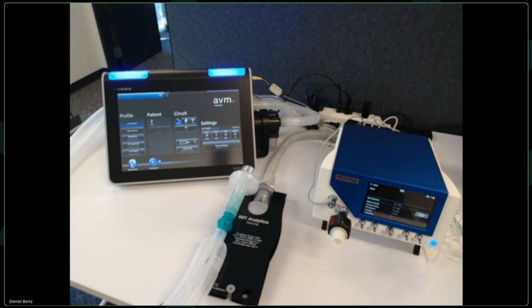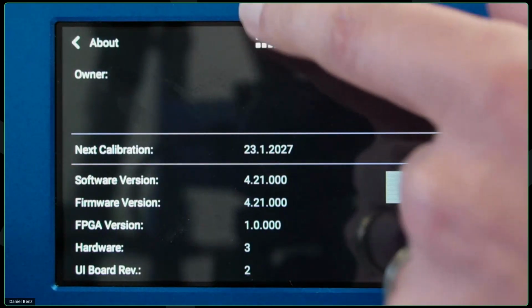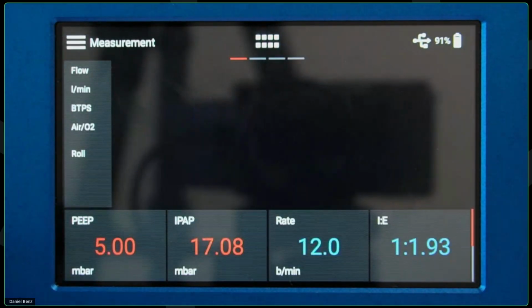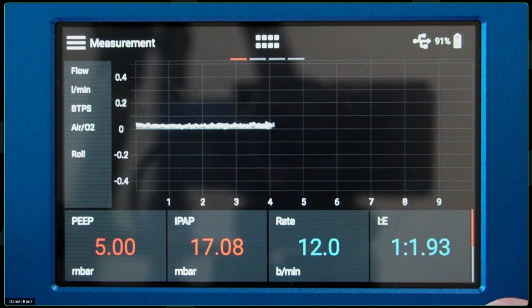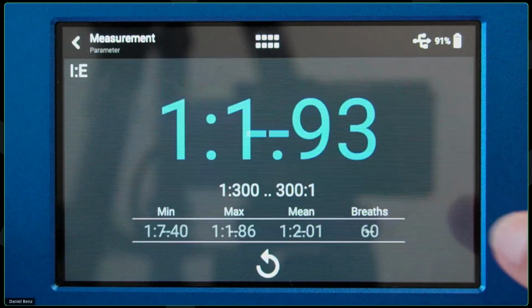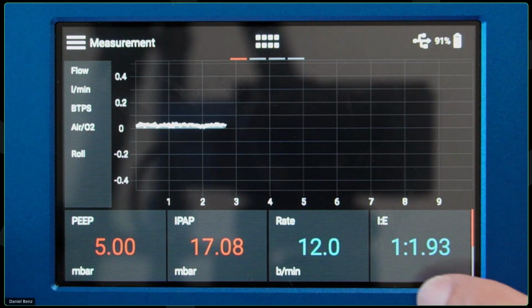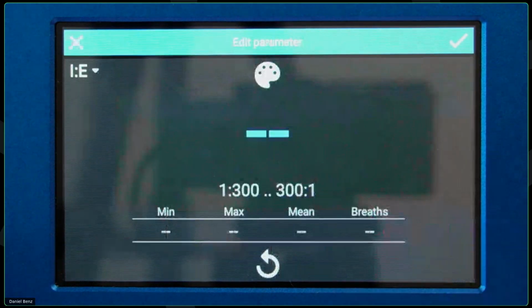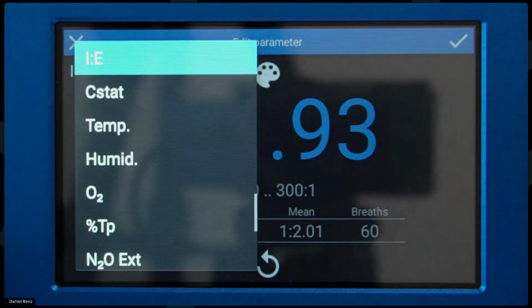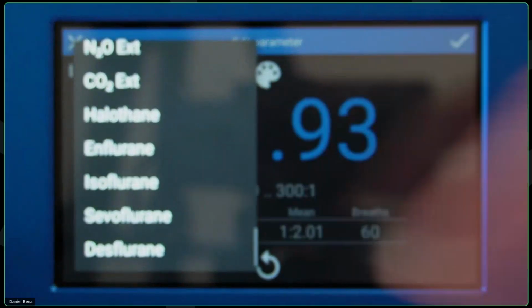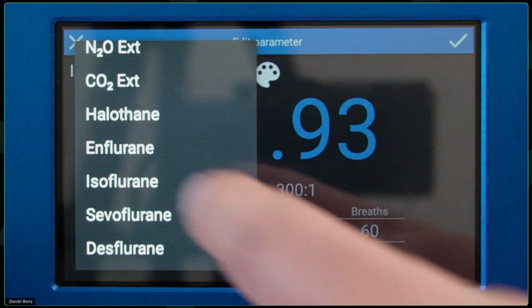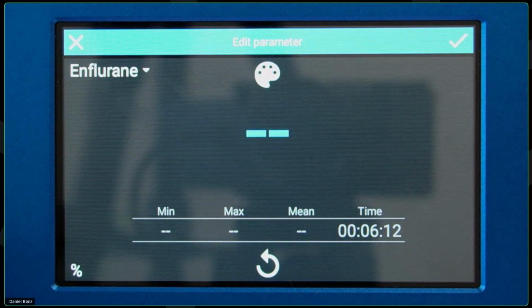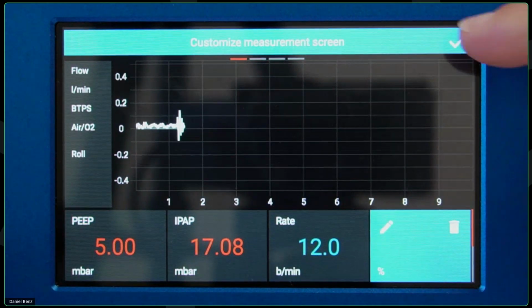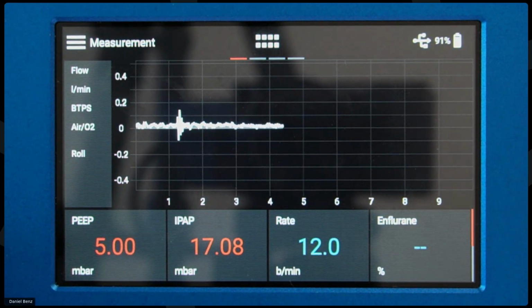And if I have an OR703 connected in my user interface, I can configure any tile I want to show the anesthetic gases. So for example, let's say I want to change this I to E ratio tile here and show one of my measured concentrations. I just press and hold, enter edit mode, change the value I want to see here, and if I scroll all the way down, you see all the anesthetic gases here. I can just pick one, and it's showing dashes now because I don't have anesthetic gases here. But that's actually how you can easily configure any of these measurements to your existing user interface.